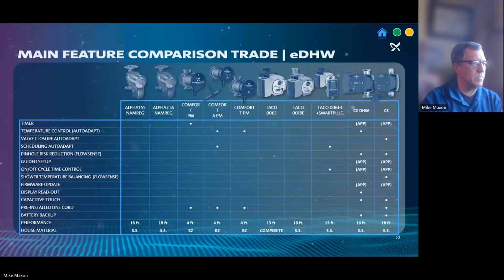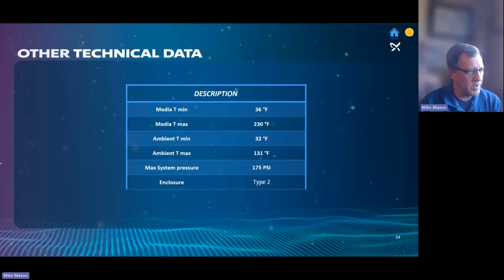So here's the competitors chart. Again, I think we blow everybody away as far as what we can do with this product. Just the fact that you don't have to wire an aquastat, I think will capture a lot. Again, max ambient of 131 Fahrenheit. Max system pressure 175. Max fluid temperature is 230, but of course, we don't like for open systems for it to be that warm. I think all you guys know that the regular systems are going to be a max of 140, and that's kind of where we like them to be. Above that, you start getting hard water deposits.